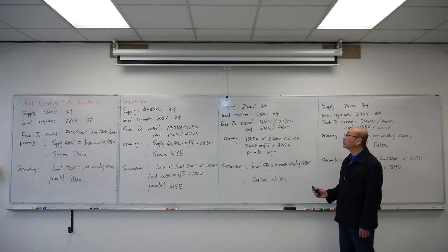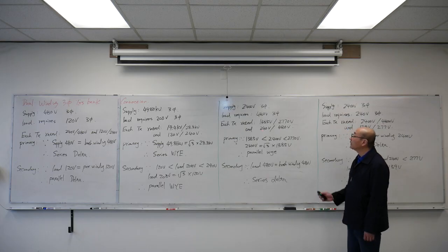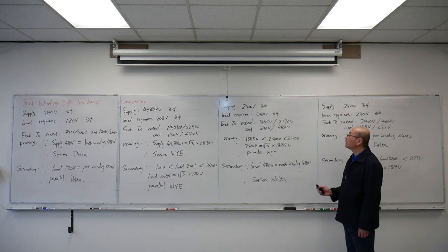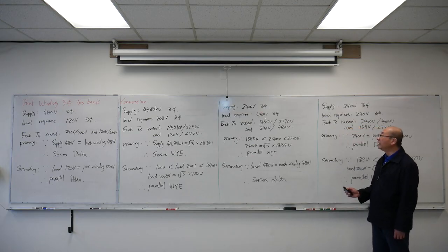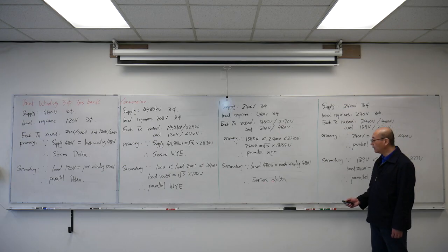Third example: supply 2400 volts, load 480 volts. My transformer is rated for 2770 and 1385, with low voltage side 240, 480. Primary side, 2400 is higher than 1385 but lower than 2770, so the number is between the two. So I check root 3 times 1385 equals 2400 volts. I'm now going to connect my primary side parallel Y. Secondary side, 480 volts equals the both winding voltage, 480 volts, so I'm going to connect the secondary side series delta.